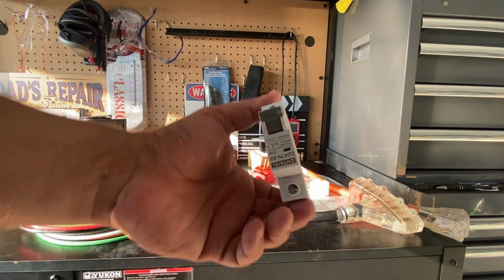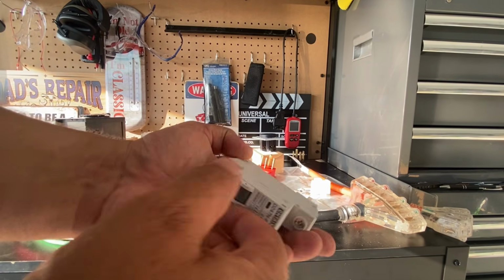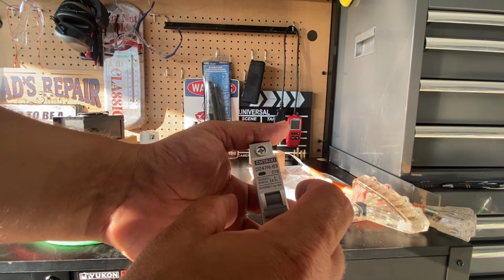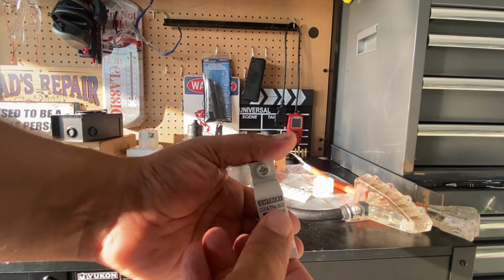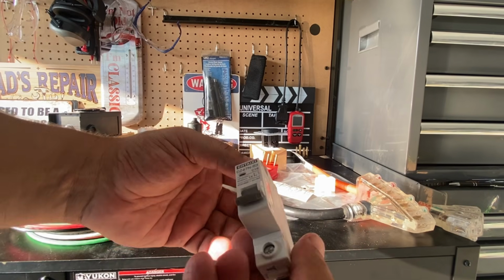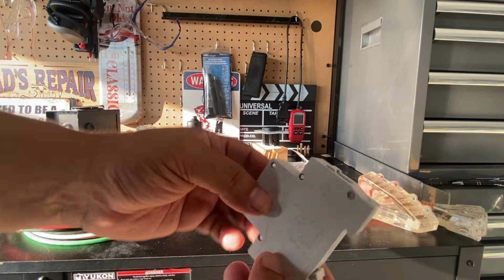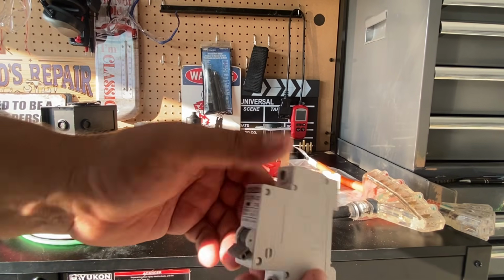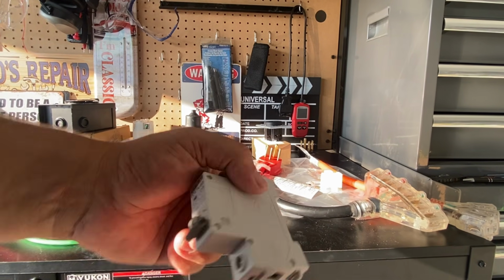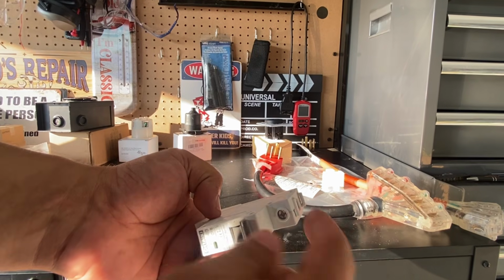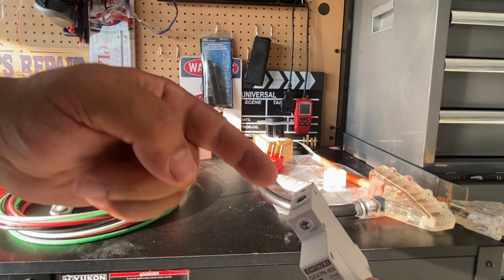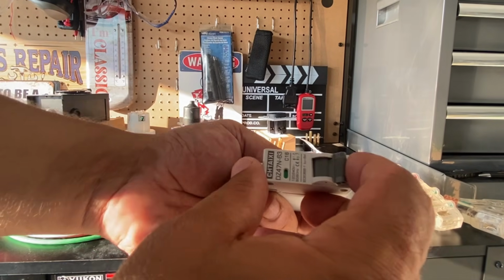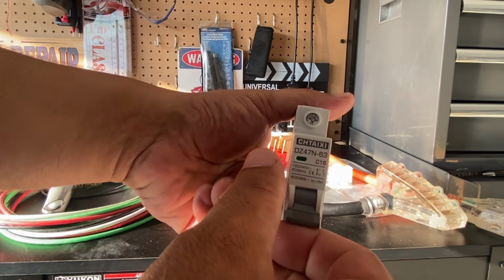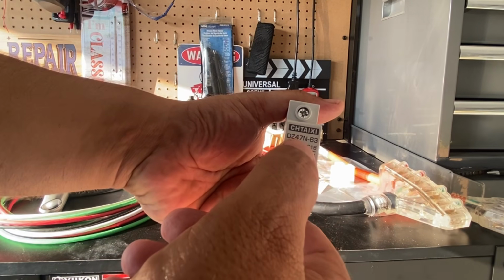This is the breaker I used. I actually used a double pole, so it's two of these side by side with a connecting pole. Again, these are not polarity sensitive for alternating current, but for DC current they are. Per this manufacturer, I can use either one and I'm okay. So the hot wire goes into here, and the other one providing power to the circuit would be over here. Green means it's not energized, red means it's energized.